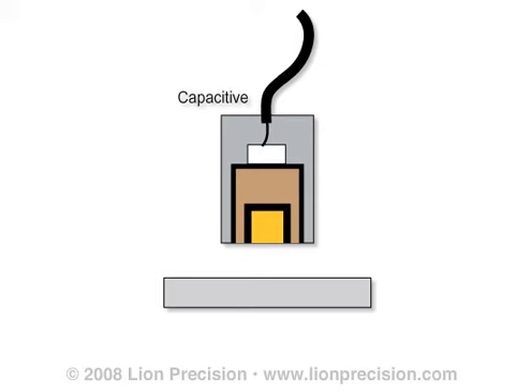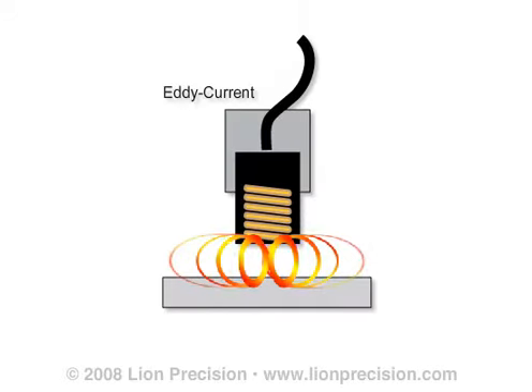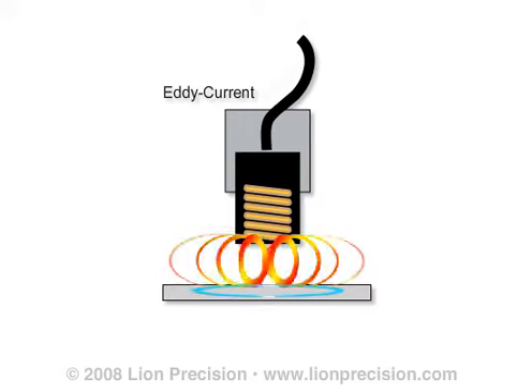Capacitive and eddy current sensors have different requirements for target thickness. The electric field of a capacitive sensor engages only the surface of the target with no significant penetration into the material. Because of this, capacitive sensors are not affected by material thickness. The magnetic field of an eddy current sensor must penetrate the surface of the target in order to induce the eddy currents in the material. If the material is too thin, the eddy currents in the target produce a weaker magnetic field. This results in the sensor having reduced sensitivity and a smaller signal-to-noise ratio.